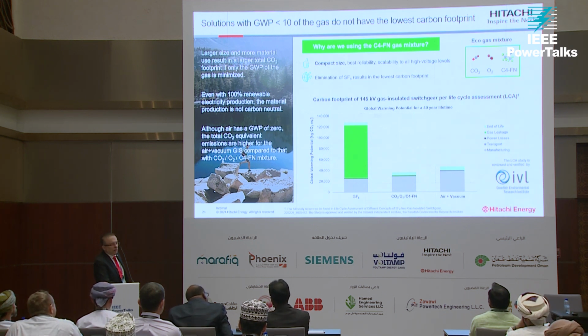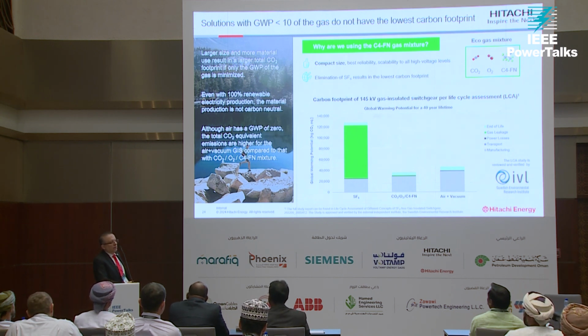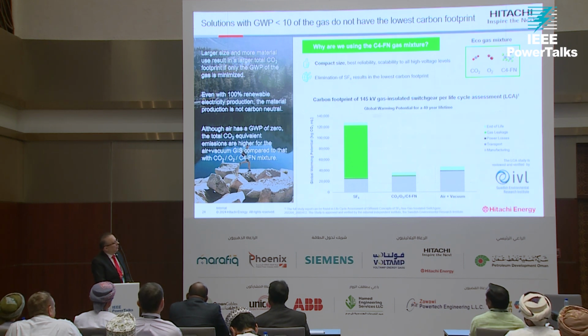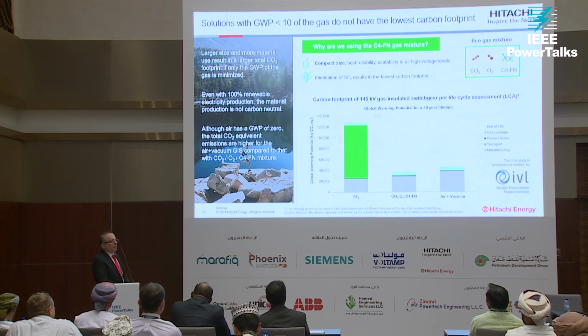In a vacuum, there's no gas, so by itself it has a GWP of 0. But vacuum technology, at higher voltage levels, isn't developed enough, so the product is bigger compared to ours. Therefore, from a whole life cycle assessment, the CO2 equivalent footprint from manufacturing is higher. The part related to gas leakage contributes only a couple of percent to the whole CO2 footprint. But when comparing air and vacuum, the product itself is almost 50% bigger.